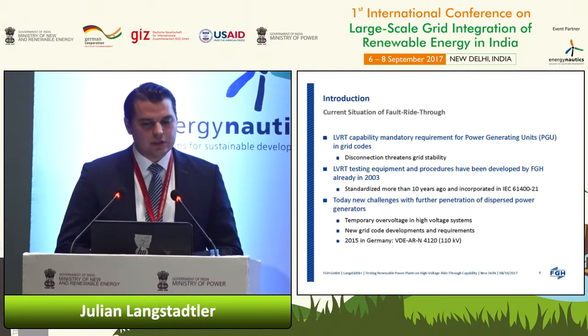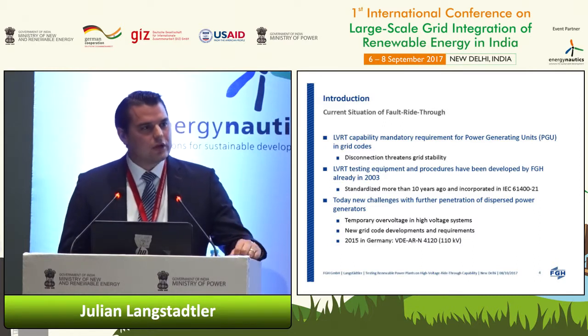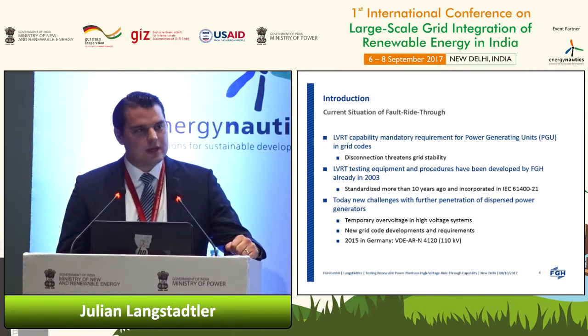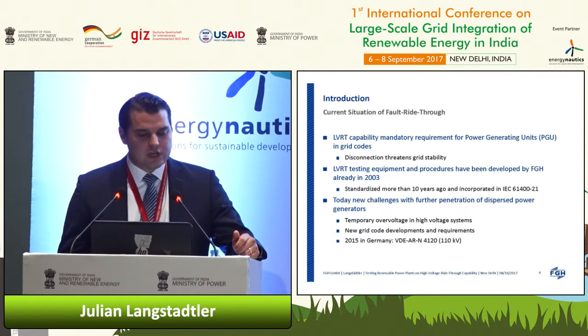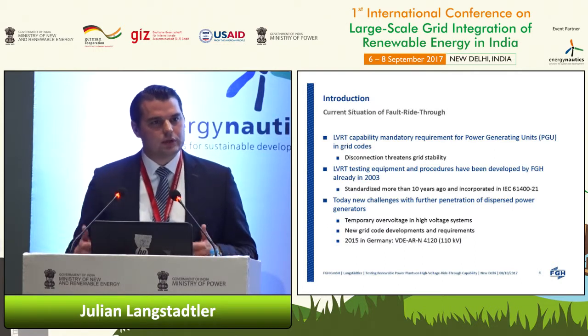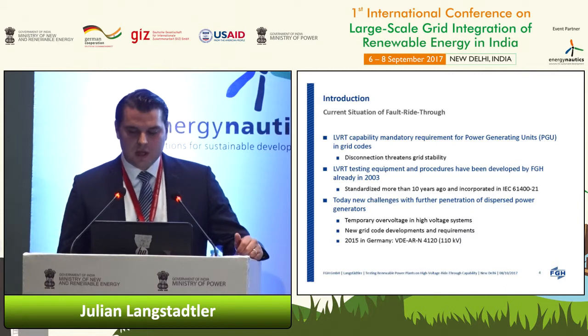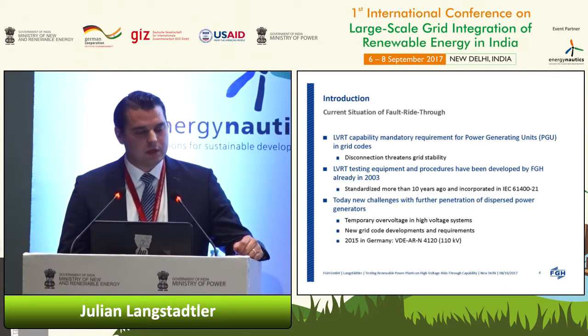So what is actually the current situation of fault ride-through? So as we already have heard several times today, an LVRT capability is absolutely mandatory for power generating units in grid codes whenever there's a significant share of renewables within the system, and the renewables are more or less system relevant, whenever their disconnection would otherwise threaten the grid stability. And so far that is state of the art today, and also incorporated in the IEC standard. And FGH already developed the testing equipment and procedures already in 2003, and our procedures were also later on incorporated in the IEC standard for wind turbine 61400-21 for power quality.